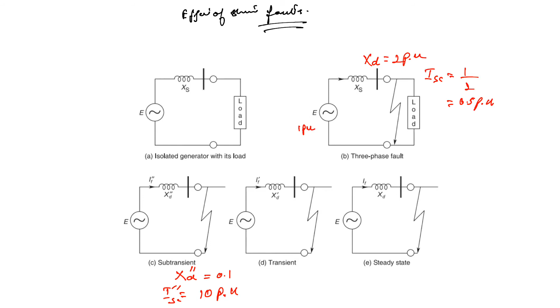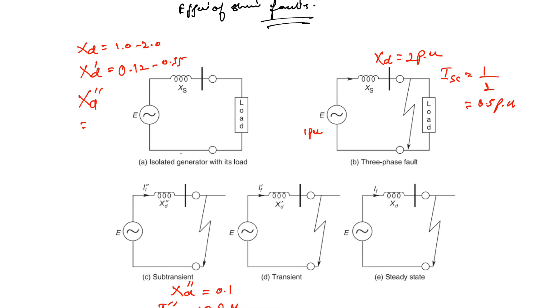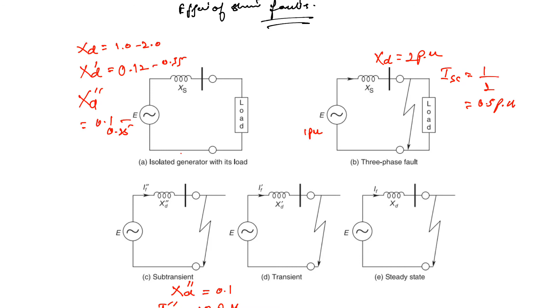As you already know, whenever the fault occurs, we have the subtransient period for a few cycles, then the transient period, and then the steady state period. For a typical turbo alternator, the steady state value of this impedance is from 1 to 2, for transient the value is 0.12 to 0.35, and for the subtransient the direct axis reactance value is 0.1 to 0.25. So this is the subtransient period in which you will see the value of the current is very high. That is, it is 10 times the normal current.